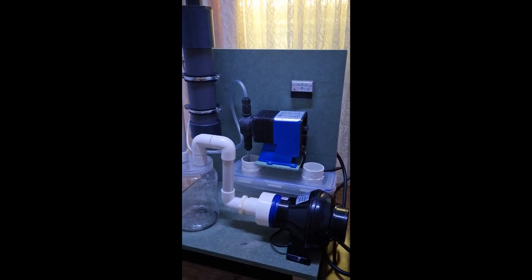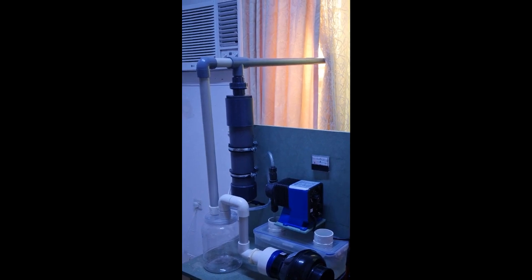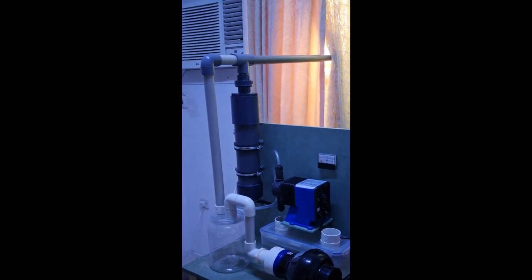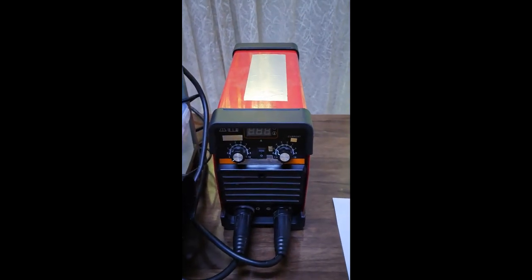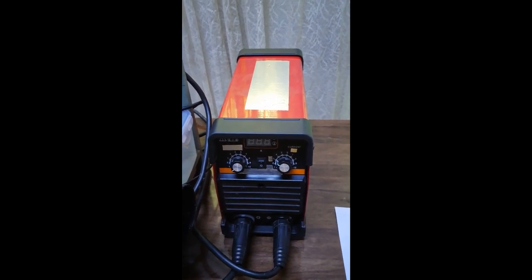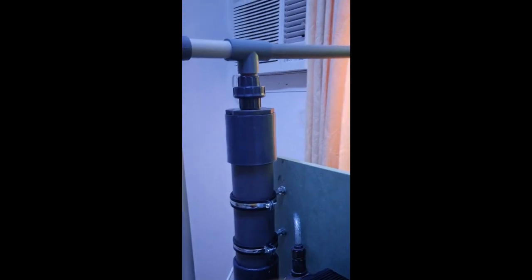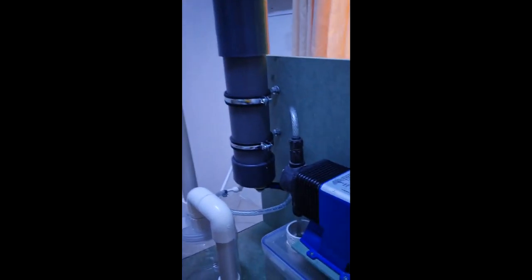What I'm showing here is just a prototype of a sodium hypochlorite generator. It basically consists of a DC power supply, and this one is oversized at about 200 amps while the required one could be 50 amps only. Then we have the electrolyzer chamber and the cathode and anode are connected by power cables to the DC power supply.